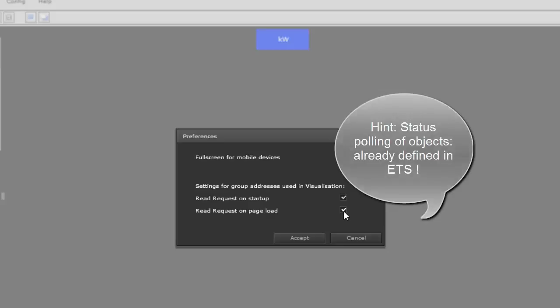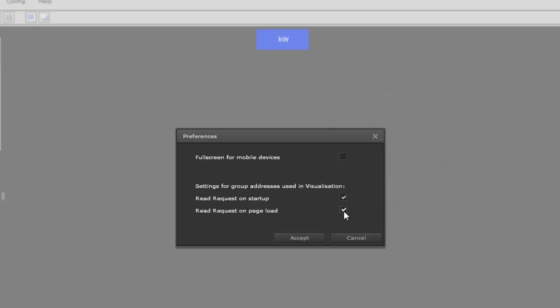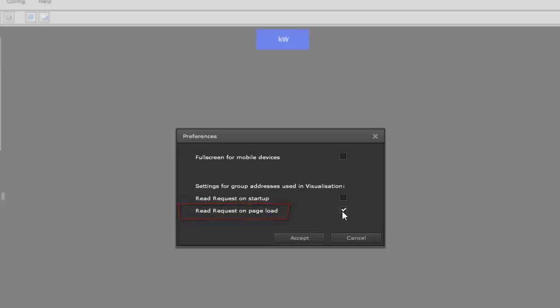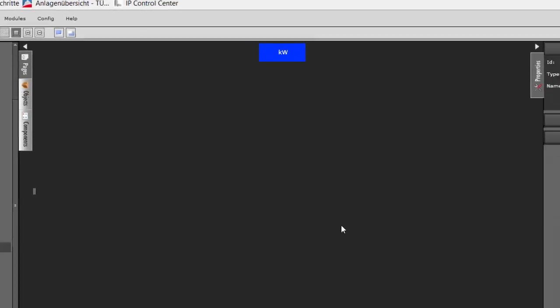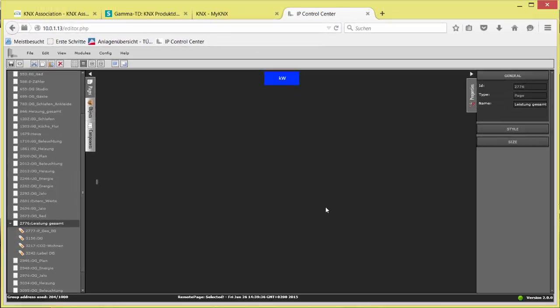If many group addresses are set to polling, then instead of read requests on startup, which polls them all at one time with parameterized polling rate, read request on page load should be ticked. This reduces the polling telegram rate after reset because only the current page-related group addresses and objects will be updated. If the IP Control Center has valid status values, it will not continue with polling.